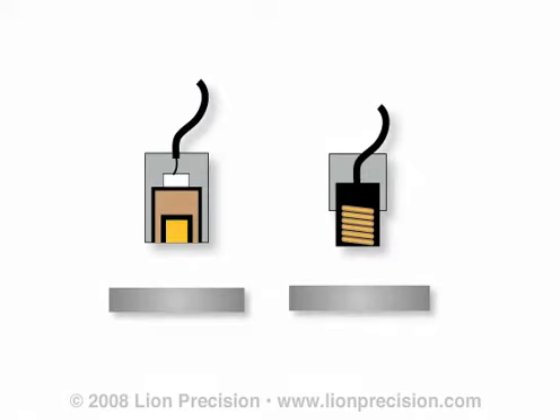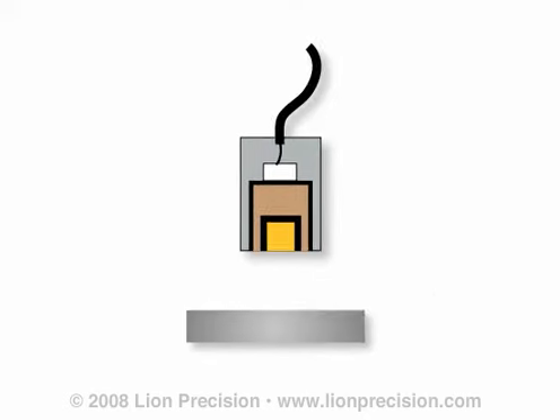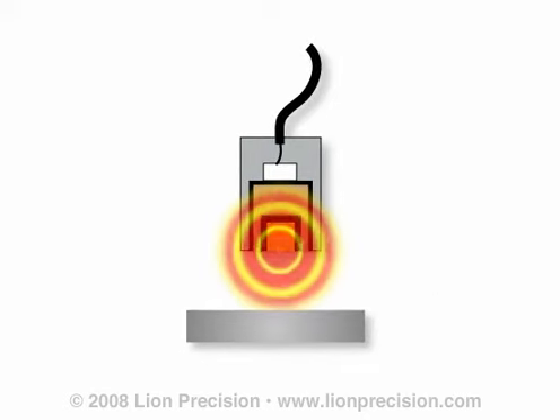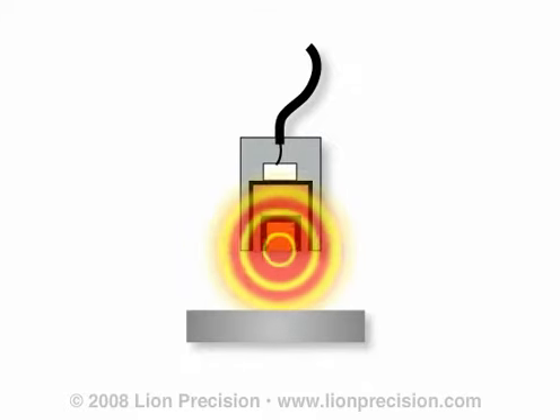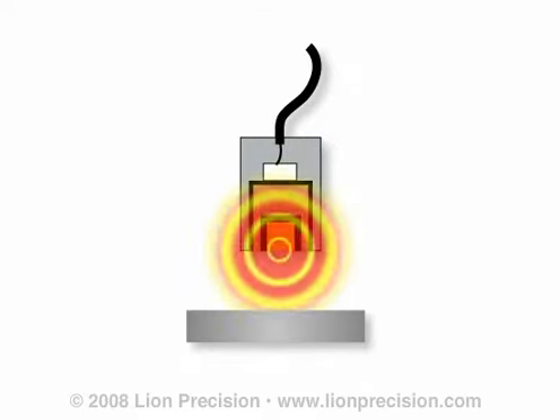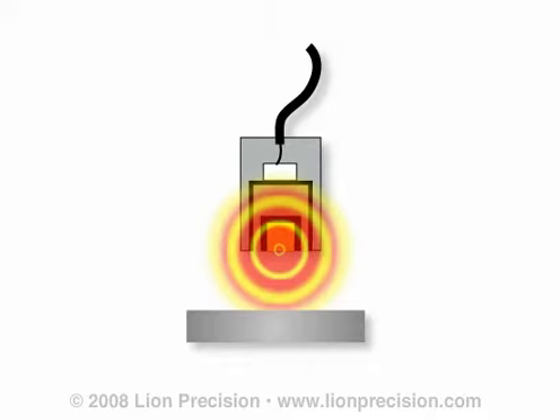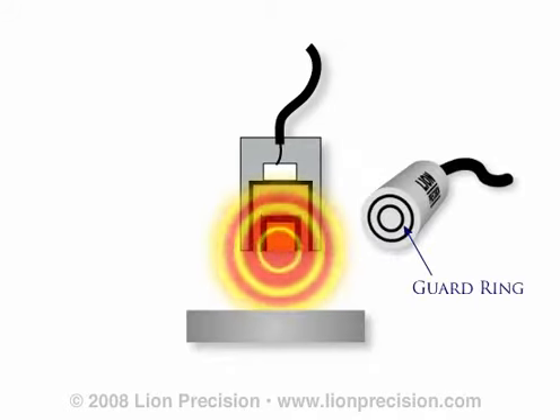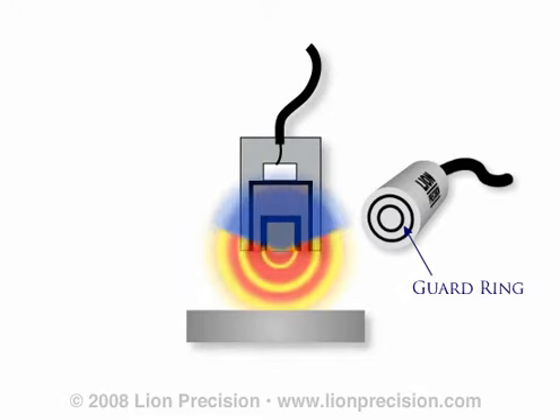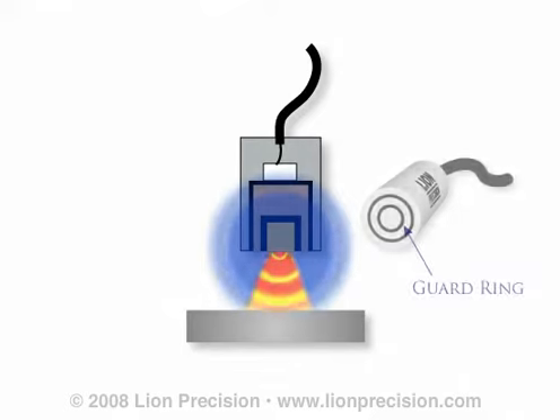Capacitive and eddy current sensors use different techniques to determine the position of the target. Capacitive sensors, used for precision displacement measurement, use a high-frequency electric field, usually between 500 kHz and 1 MHz. The electric field is emitted from the surfaces of the sensing element. To focus the sensing field on the target, a guard ring creates a separate but identical electric field which isolates the sensing element's field from everything but the target.